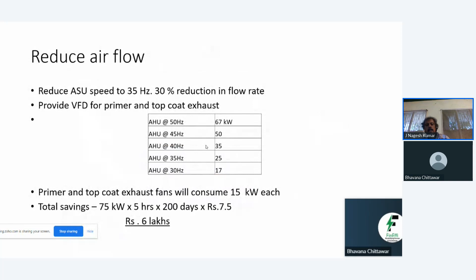He is looking at the system, 16 to 18 units. Ventilation rates are designed for that. Now it is only 8 units. So where do we cut corners? Reduce the frequency of this. At the same time, as the input air reduces, the exhaust air also can be reduced. Here the fan has a damper. Further close the damper, keeping the draft inside the oven the same. So this energy also reduces. This is another example where getting slightly deeper can result in huge savings in energy consumption.